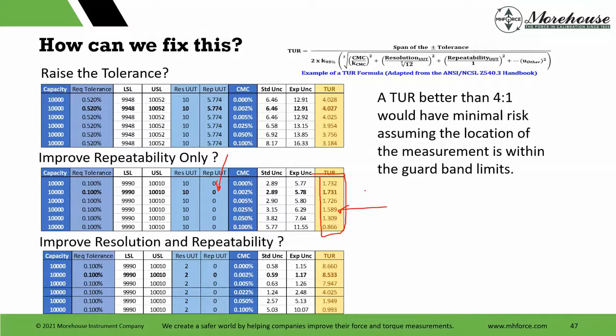Air Force, this is one that I pick on Air Force a little bit because their requirement is 4-to-1. That's why I'm on the 4-to-1. You may not have that requirement, but improve resolution and repeatability. We did this. There's a paper online in those documents and tools. We had an instrument come in, specifically this scale, and sent it out. They retooled the equipment. They put a new display on it. They did a lot of other things to it, and they made it better.